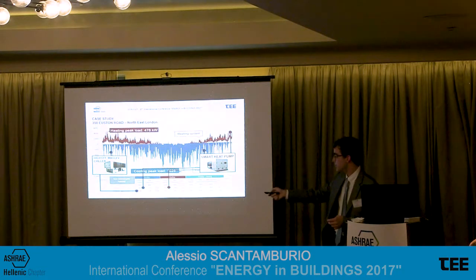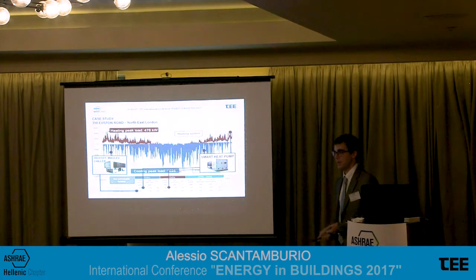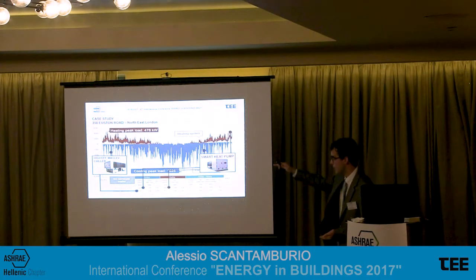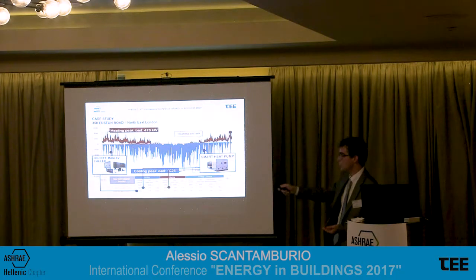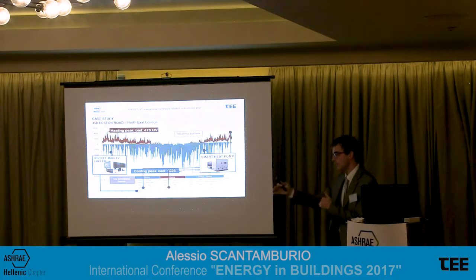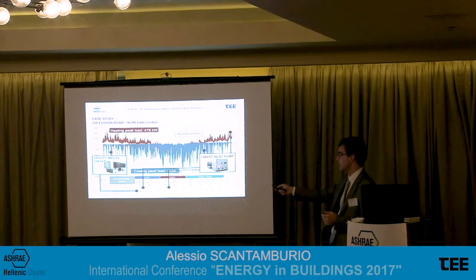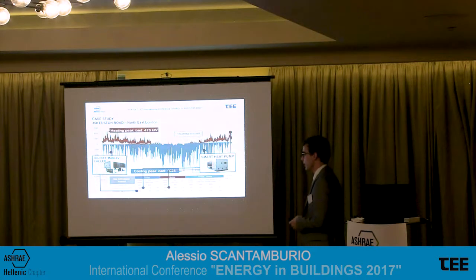But the maximum heating peak load was more or less 500 kilowatts, so this means that the unit produces, again, more or less 500 kilowatts in terms of cooling capacity. Then, to get the extra cooling capacity needed, we sized an additional maglev chiller with magnetic bearing, oil-free. Okay, so this was the plan.